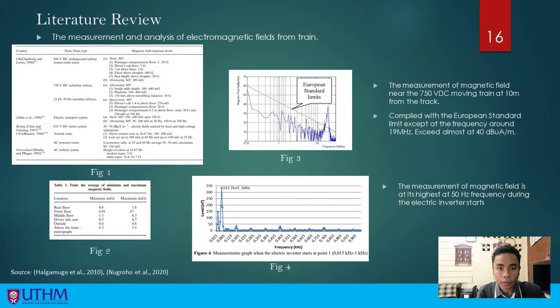As you can see, here are several measurements and analyses of electromagnetic fields from trains in other countries. The measurement varies with the types of train power supply such as 600 VDC, 750 VDC, and 25 kV AC of 50 Hz mainline railways at different locations on the train. For figure 2, the average minimum of the magnetic field varies slightly depending on the location. For figure 3, the measurement result of the magnetic field near the 750 volt DC moving train at 10 meters from the track complied with the European standard except at the frequency of 19 MHz. For figure 4, the measurement during the start of the electric inverter train is at its highest at 50 Hz frequency.